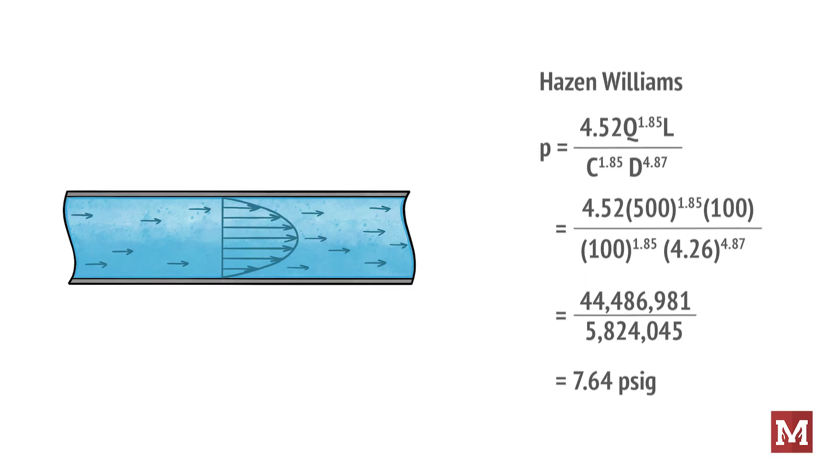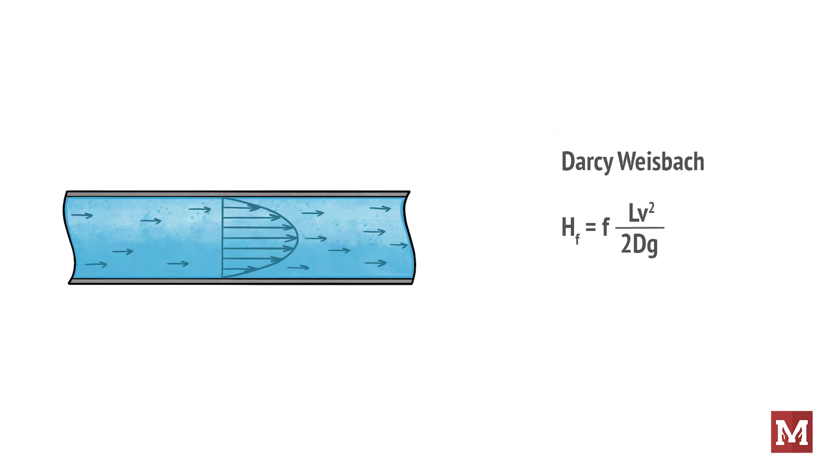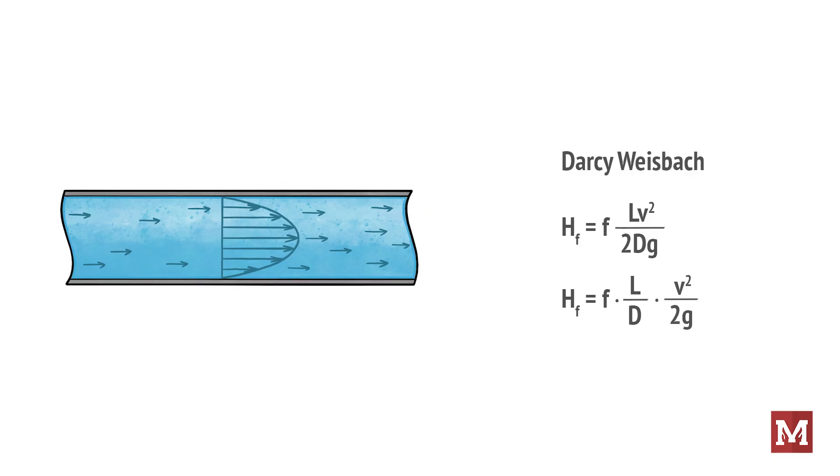Now let's calculate pressure loss using Darcy-Weisbach method. This method measures pressure loss in terms of feet of head. So the equation is H sub f equals f times ratio of the length of the pipe divided by its inner diameter times the velocity of the fluid in the pipe squared divided by twice the gravitational constant.